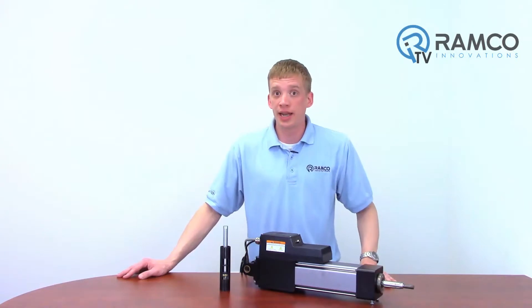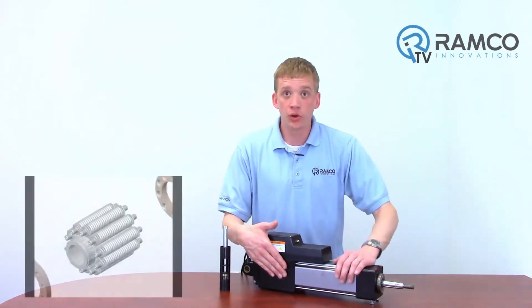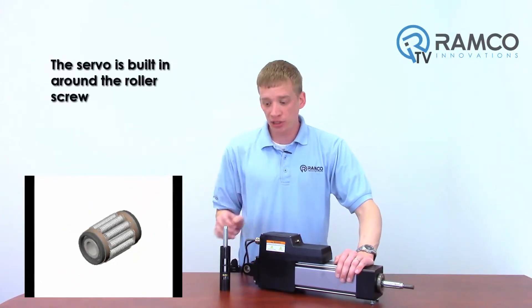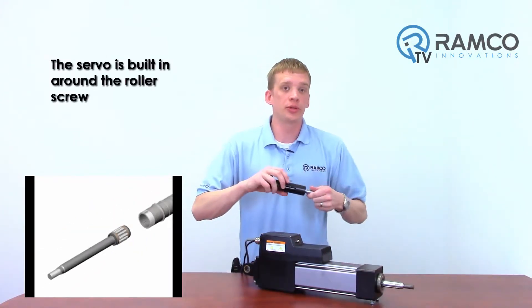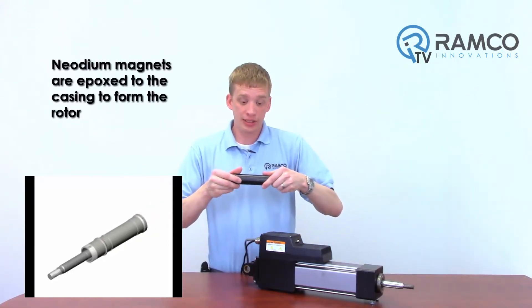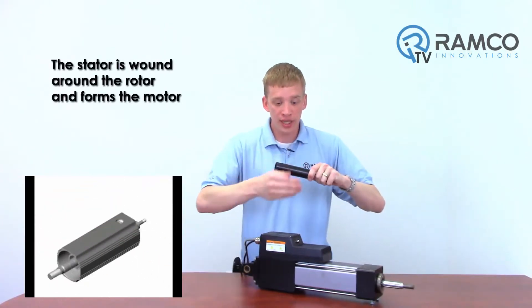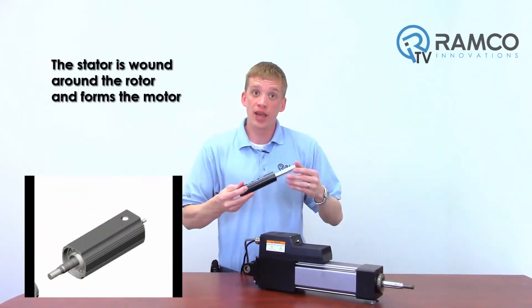I mentioned this is a servo-based actuator. This is actually not a servo coupled to a roller screw, but the servo is actually built in around the roller screw. Neodymium magnets are epoxied on the outside of this casing — now this becomes your rotor. The stator is wound around the outside of the rotor. Now we have a motor.